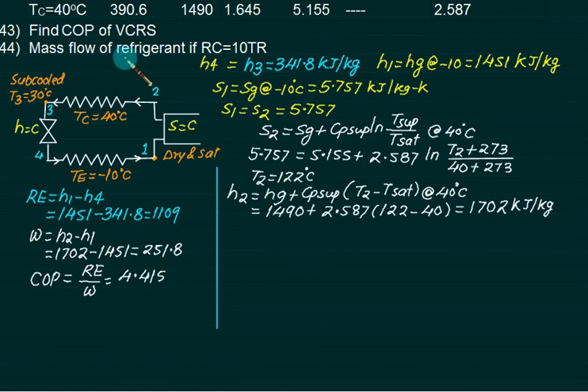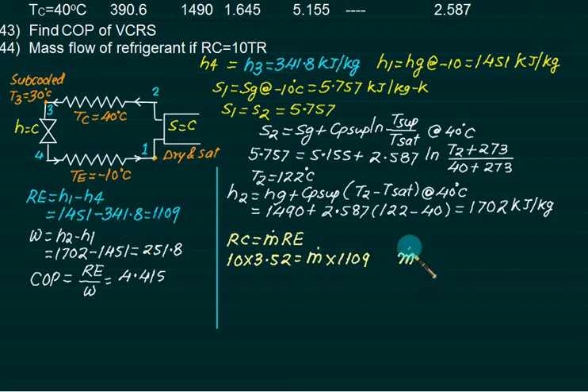To calculate mass flow rate of refrigerant, Rc is given as 10 TR. Rc equals m dot multiplied by Re. 1 TR equals 3.52 kilowatts. Re is known to us as 1109. From this, we can calculate m dot as 0.03174 kg per second.